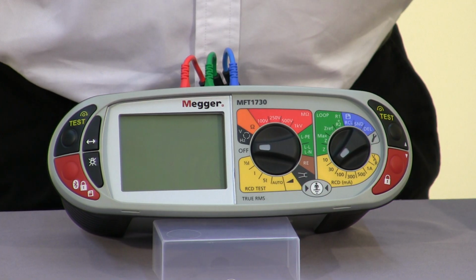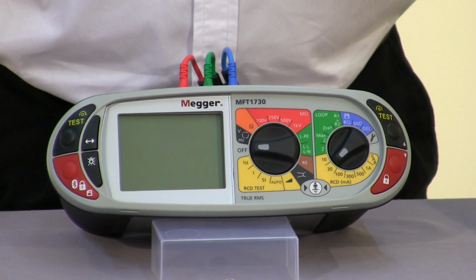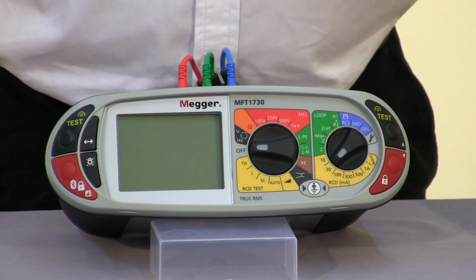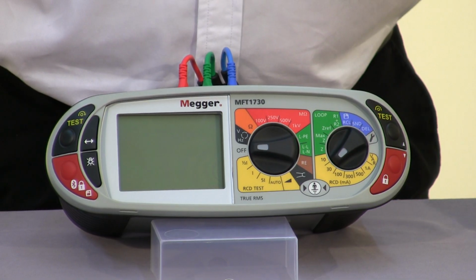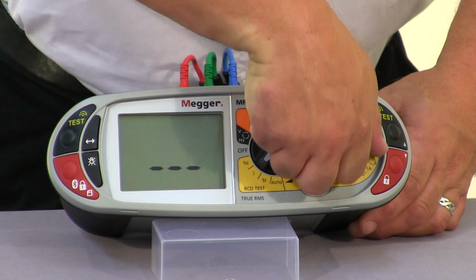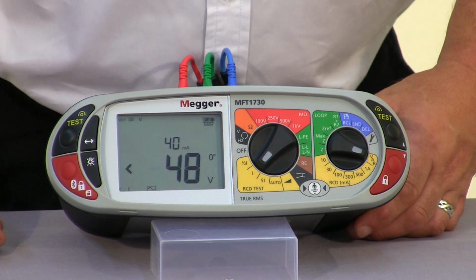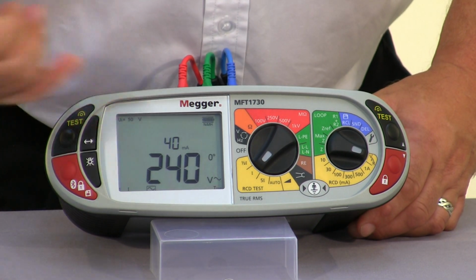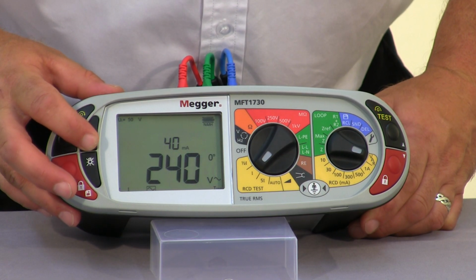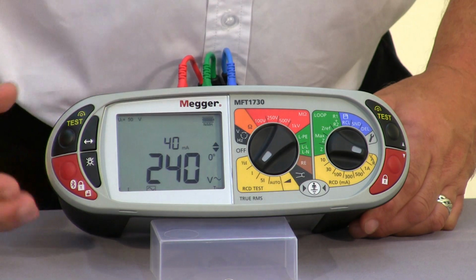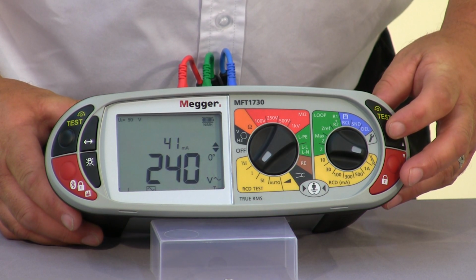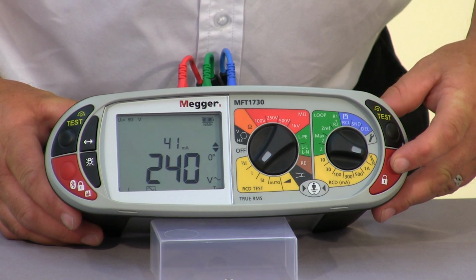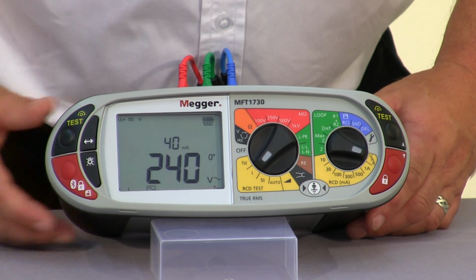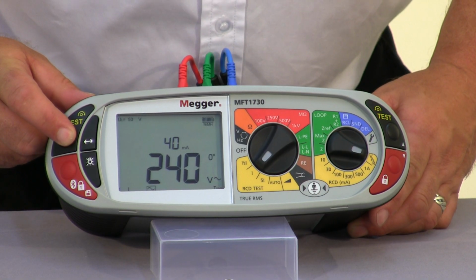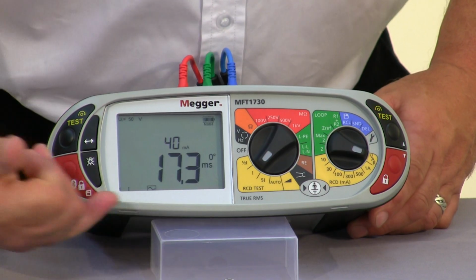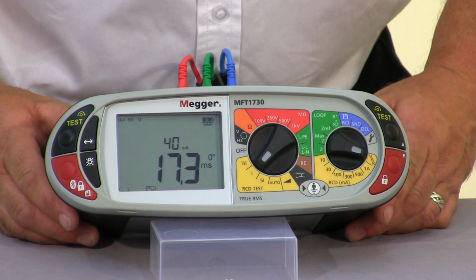The variable RCD test that we have available on the MFT1720 and 1730 will allow you to dial up a non-standard RCD trip current. So if I show you, for example, a 40 milliamp RCD test, as you can see, it's actually defaulted to that. But what we can do is by selecting the function key, we have our up and down arrows, and using the up and down, you can see quite clearly it's very simple to select the value of the test that we want. So turning the selection off, pressing the test button, which will do a times one test, and as you can see, we've got a reading of 17.3 milliseconds.